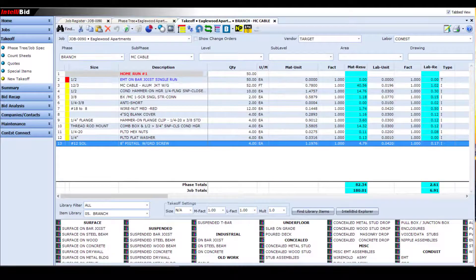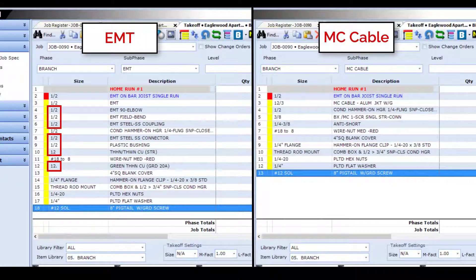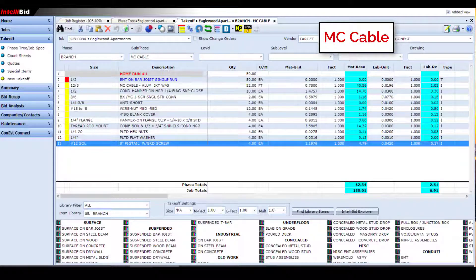Now, what smart substitution has done is use the latest NEC code tables to replace the EMT conduit in our assembly with MC cable. You'll notice that it also changed out the EMT fittings with those needed for MC cable. As I jump back and forth between the original EMT version and the new MC cable one, you'll notice the changes in the material and labor results as well.